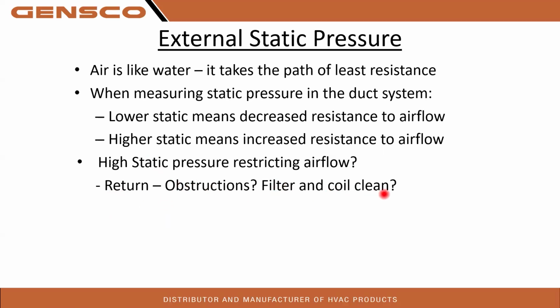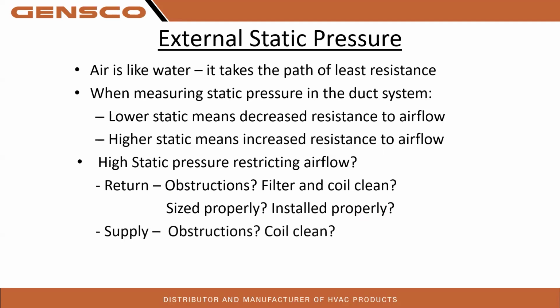Is the filter and the coil clean? Those are going to affect your airflow through that coil. And we can actually take a static pressure across that coil to see, is the ductwork sized properly or installed properly, right? So if we're installing a new system and the homeowner wanted a little bit more oomph and we're doing a 4-ton instead of a 3-ton, well, you're probably going to have undersized ductwork. Again, supply obstructions, is the coil clean? On the supply side, the coil comes into play again.